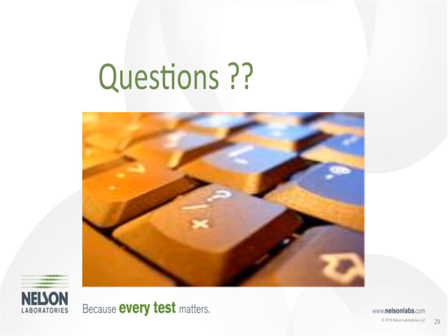Okay. So our next one is, does the intended use also consider any information from a human factors usability study? It may. Once again, there's a lot of factors that could go into intended use. When you look at a human factors usability study, you look at whether a user would not contact it because they're gloved or gowned or whatever it is. Then you can help justify, based on that study, that you don't have clinician use, and if it's not going to contact the patient, you don't have patient use. So you can use that.